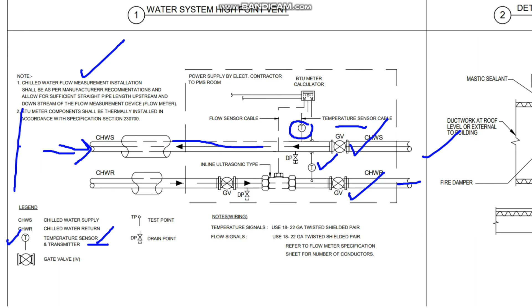Here, on this supply connection, in this application we have the item called T. If you see the abbreviation or legend here, T means temperature sensor and transmitter. This is the first item in the supply line. After that we have the gate valve for isolation purposes. When it comes to the return side, again we have another gate valve. Again we have another T, that is a temperature sensor and transmitter. And after that we have the inline ultrasonic type.